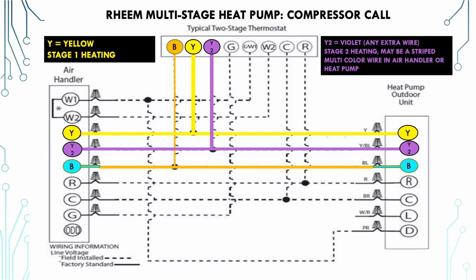When the heat pump is operating under the control of the thermostat, it's deciding when stage 2 is. Sometimes it's the air handler that's deciding it, and sometimes it is your heat pump that may decide it. Every brand and between different models is different on how they want to control that. The more computerized it is, the more likely it is to be controlled by the heat pump itself. The thermostat often has deeper controls that allow you to dictate how things are going to work, especially on communicating systems. But in this case, I use purple. It doesn't necessarily mean you've got a purple wire. This schematic for this particular model of Rheem that I pulled the diagram from says that it's a yellow wire with a blue stripe for Y2, and that is fairly common.